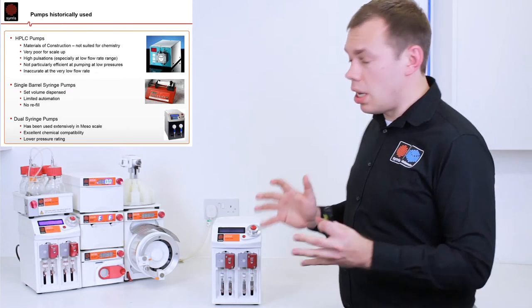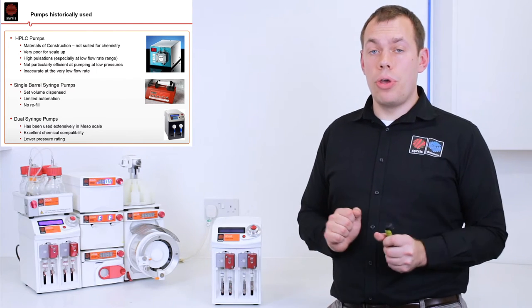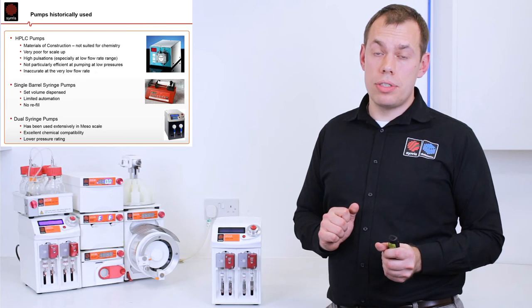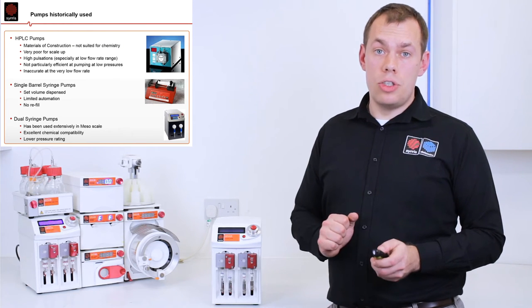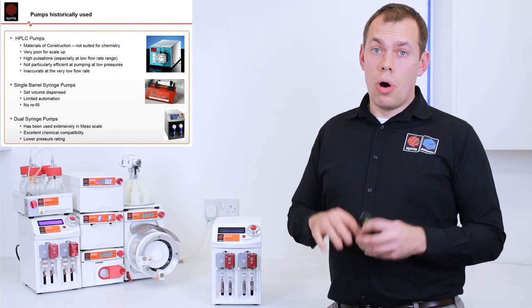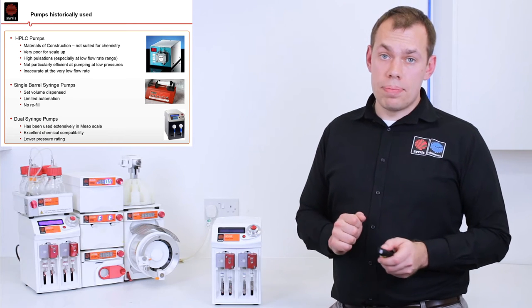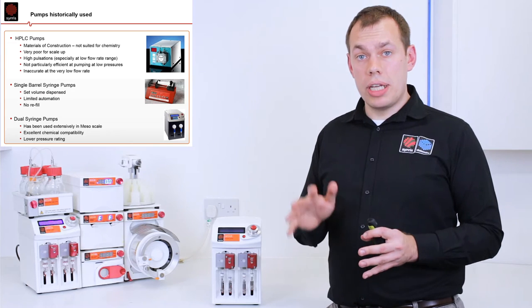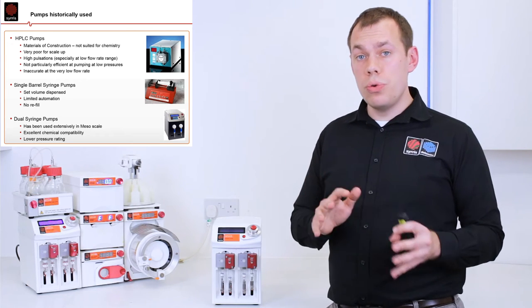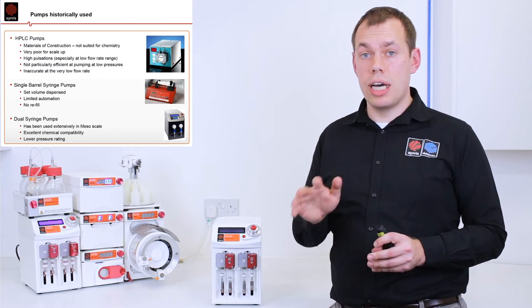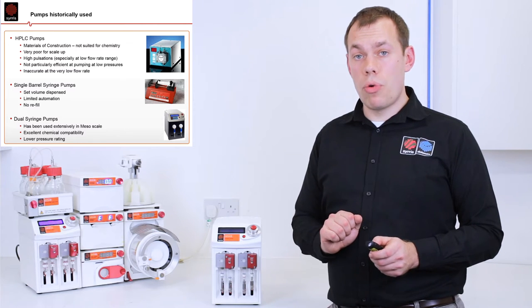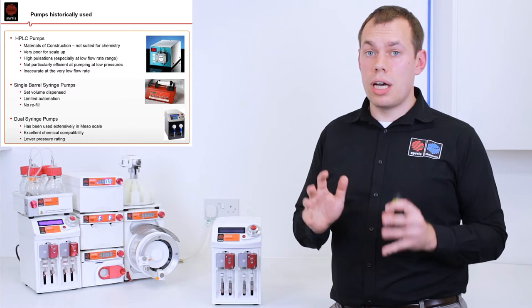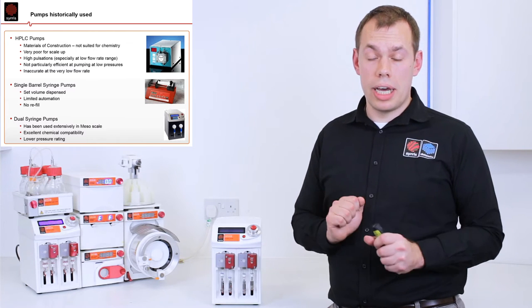Historically, people who were starting with flow chemistry were using three types of pumps. HPLC pumps, single barrel syringe pumps and dual syringe pumps. All those pumps have drawbacks. HPLC pumps are mainly designed for operating at high flow rate and high pressure. And therefore they lose a lot of their precision and accuracy at lower pressures and lower flow rates. Also the material of construction is mainly metal so they are not as highly chemically resistant as you would like.